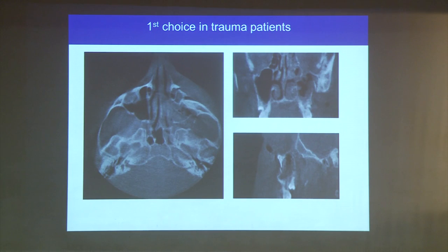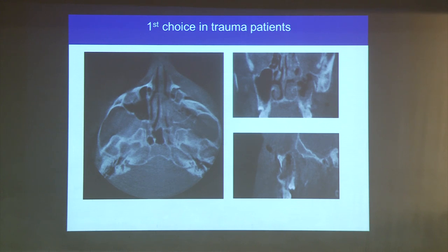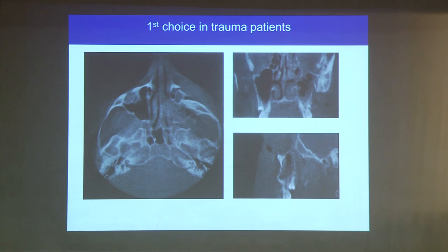Of course — and this is the next advantage — if you make a reconstruction in multi-planar levels, you always have the same image quality. In older CT scanners you have stepping artifacts; here you have the same image quality in all levels. And the level of metal artifacts is also reduced compared to CT scanners, which is very important regarding the oral cavity with all the metal from dental restorations in place.